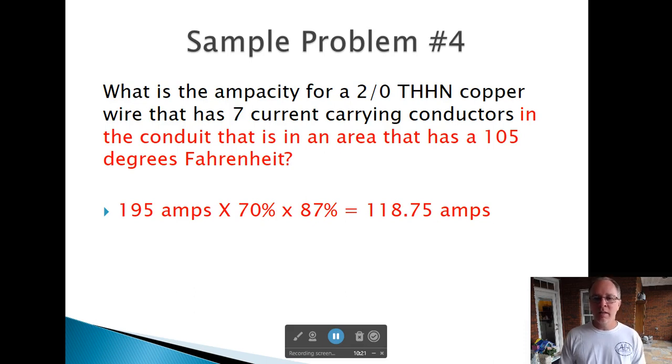So we've got 0.87, which is the multiplier for a 105 degree ambient temperature. Now that 195 amp 2-Aught wire is only good for 118, 119 amps. So we don't want to get it as hot. Amperage produces heat. It's going to produce more heat at 195 amps than it will at 118. But we're keeping the amperage lower because of the ambient temperature and other current-carrying conductors in there.